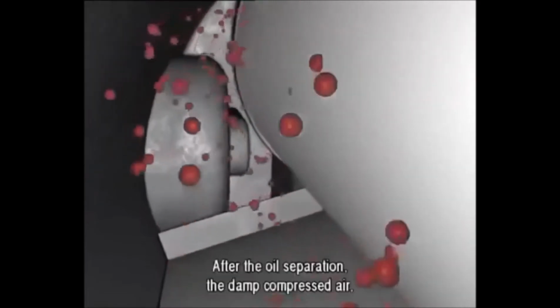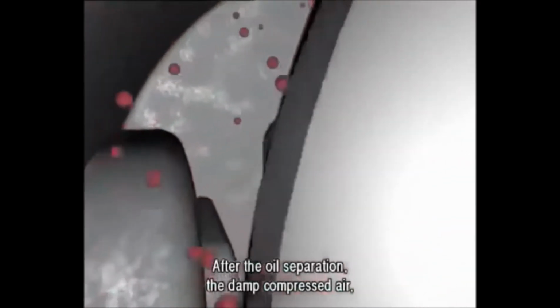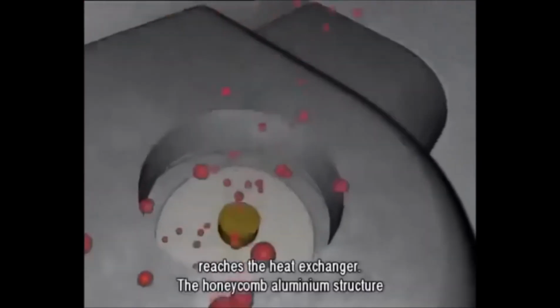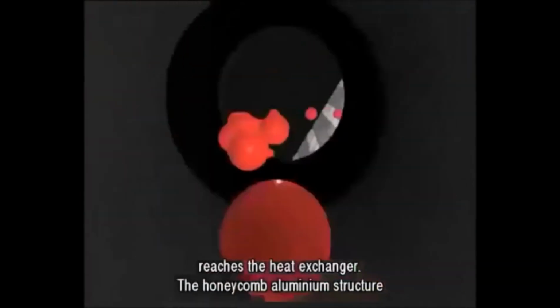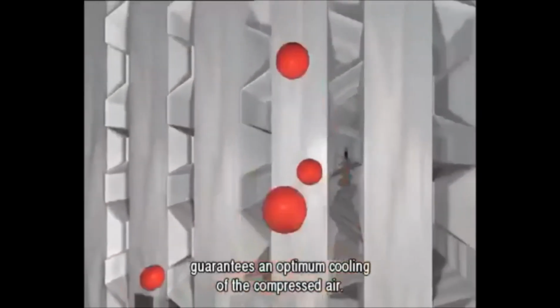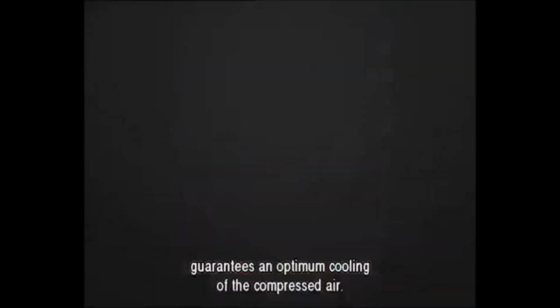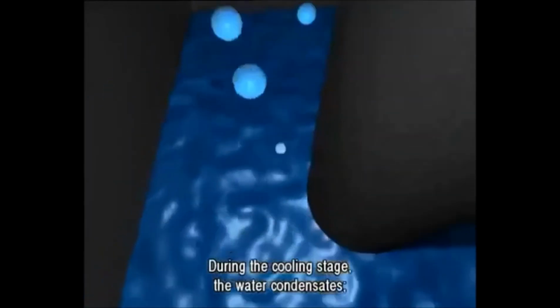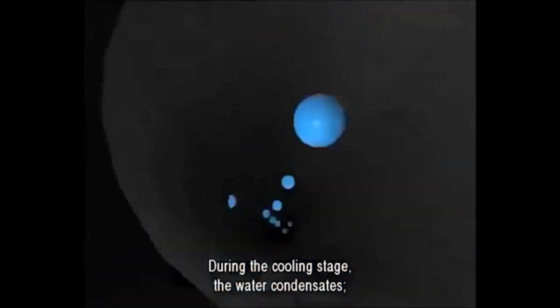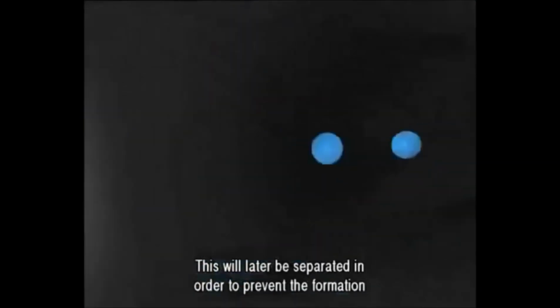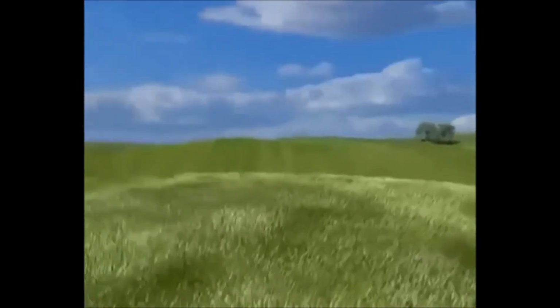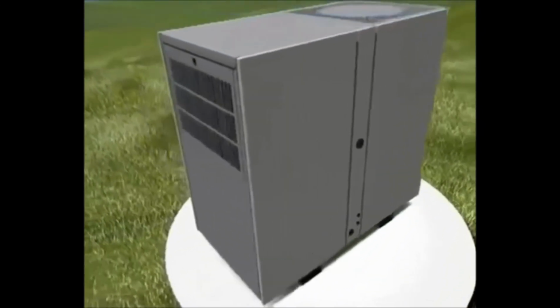After the oil separation, the damp compressed air reaches the heat exchanger. The honeycomb aluminium structure guarantees an optimum cooling of the compressed air. During the cooling stage, the water condensates. This will later be separated in order to prevent the formation of too much condensate in the air distribution lines.